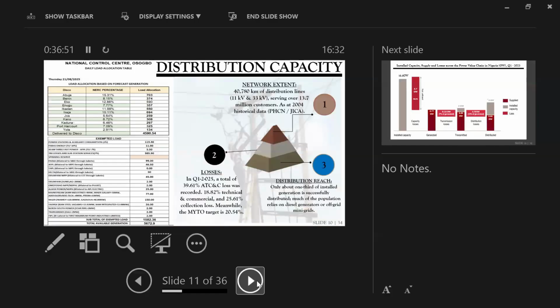Then this is distribution capacity. I was able to bring our load allocation based on forecast generation, just to show you an example of how load is being shared between GenCos, and to show you load exempted. Load exempted has to do with the bilateral agreements we have with other companies, it has to do with our losses, and it has to do with spinning reserves. And you can see that we don't have spinning reserve at all, which creates more problems in running the grid. That's why I was telling you that we need to thank our crew in NCC. They are doing a good job when they run into emergency.